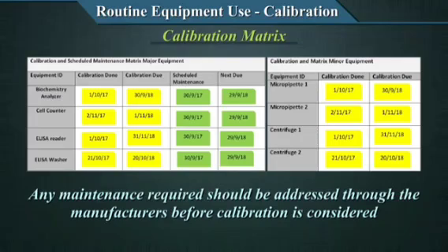So at this point, what about the maintenance that we are talking about? There will be minor repairs required for all your minor equipment also. When a major equipment manufacturer comes for their scheduled maintenance and calibration, whatever is due, they will first do a maintenance, and they will analyze the equipment for accuracy, precision, etc., and then they do the adjustment and then calibrate.